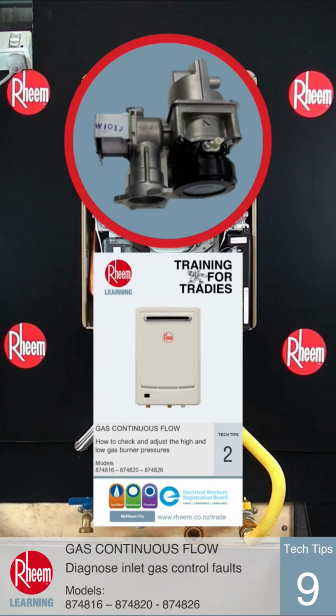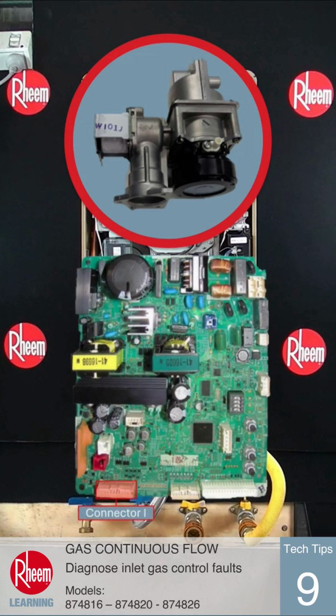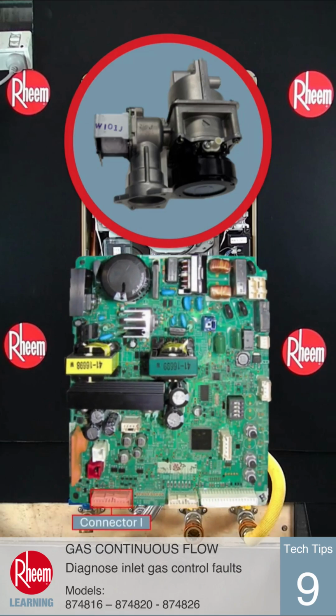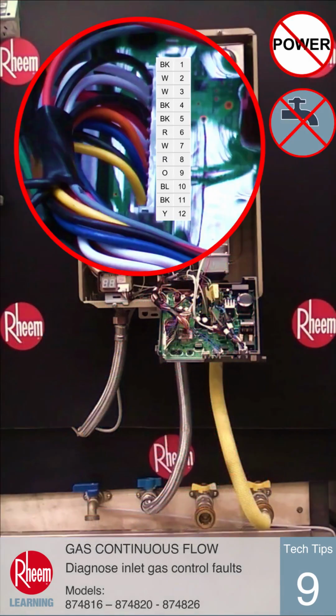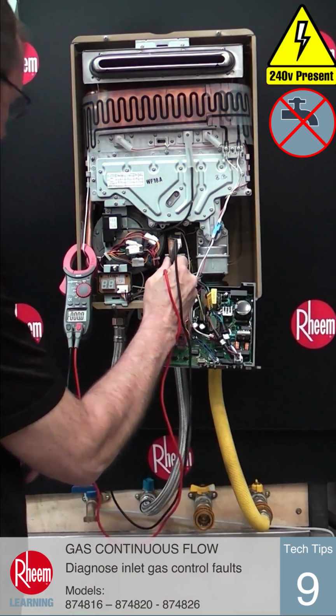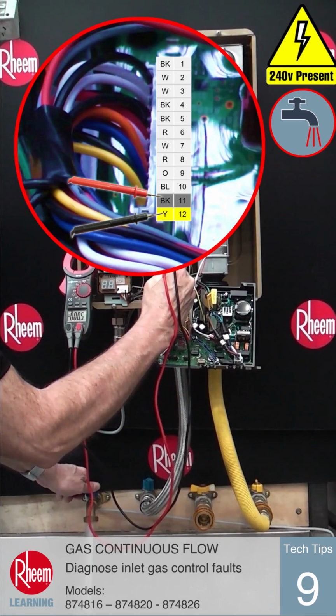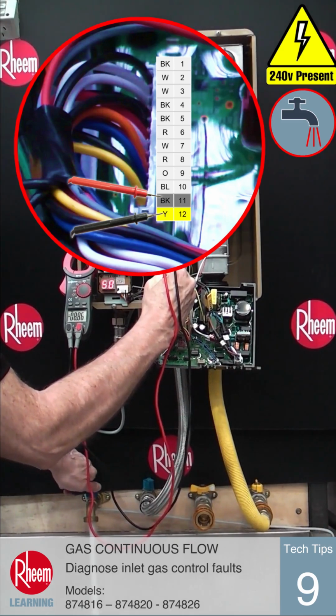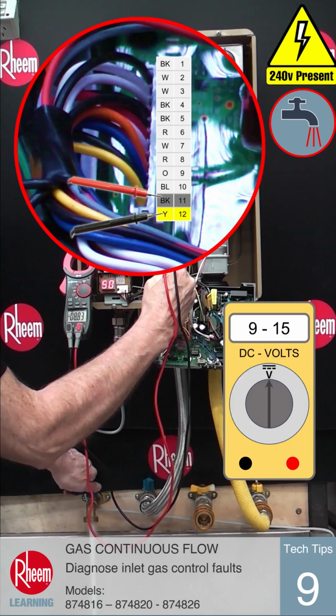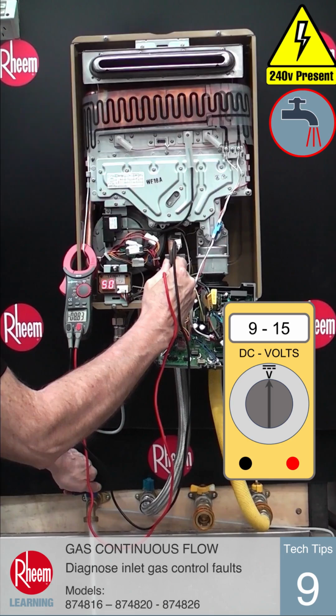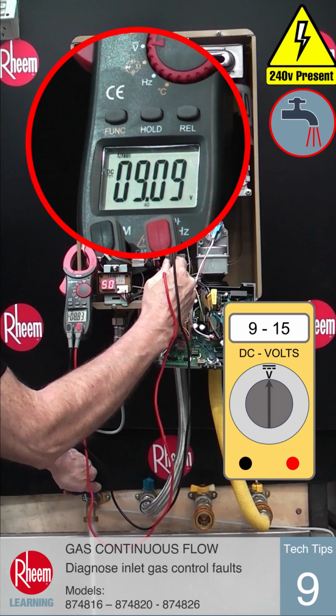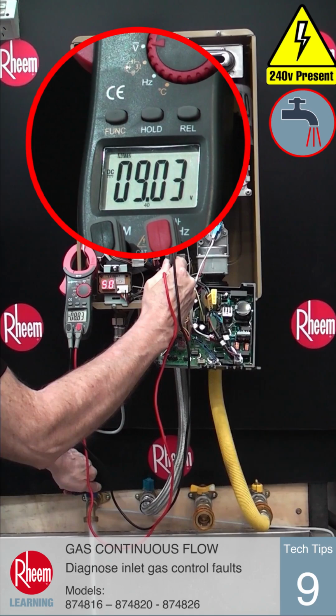If this has already been done, we can start electrical testing using a multimeter to see where the fault is inside the unit. Remove the screw and pull out the PCB to locate connector I. We will refer to pin numbers and the colour of the attached wire throughout these tests. With power on and water flowing, use a test meter to measure the voltage between pin 11 black and pin 12 yellow. The reading should be between 9 and 15 volts DC. If there is no voltage detected, the PCB should be replaced.